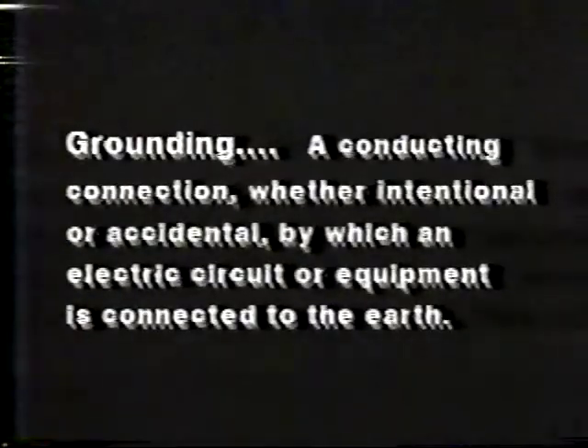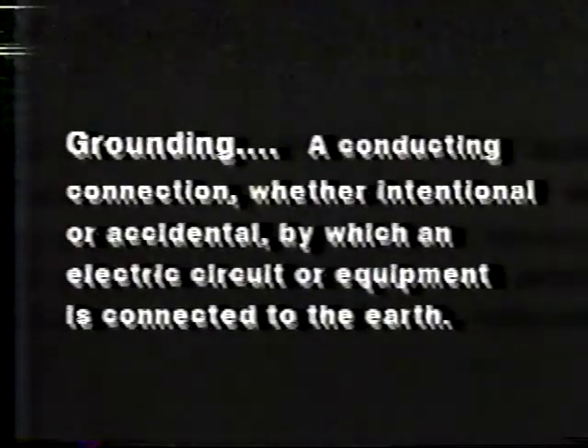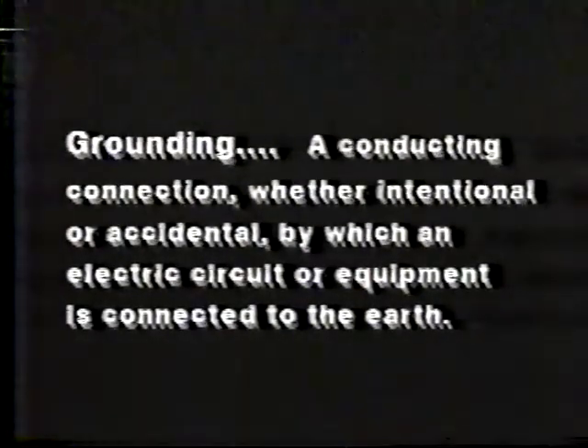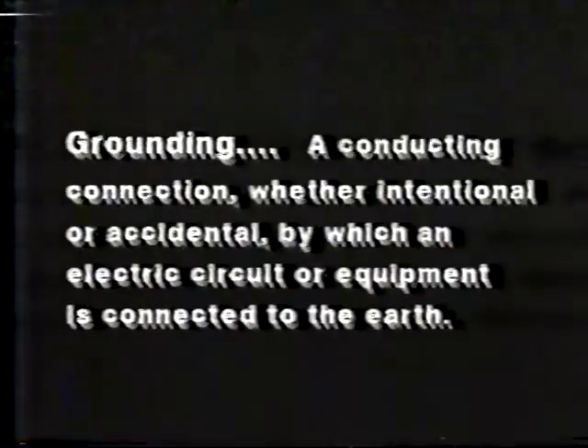Grounding: a conducting connection, whether intentional or accidental, by which an electric circuit or equipment is connected to the earth. Equipment grounding consists of the grounding of all non-current carrying metal frames, supports, and enclosures for electrical conductors and equipment.